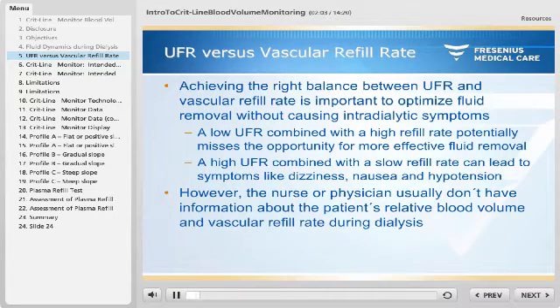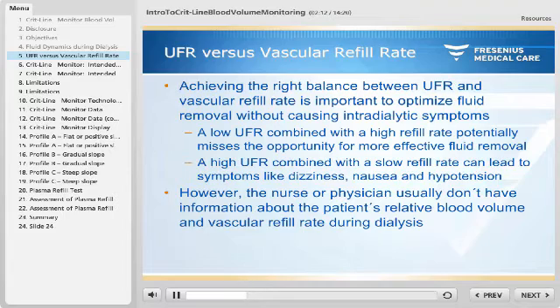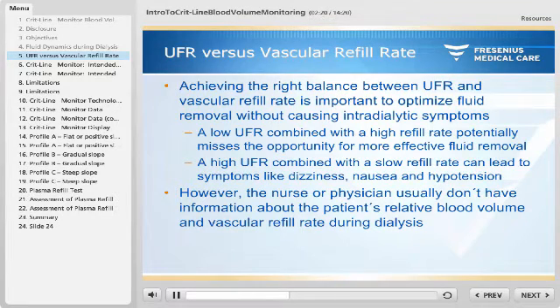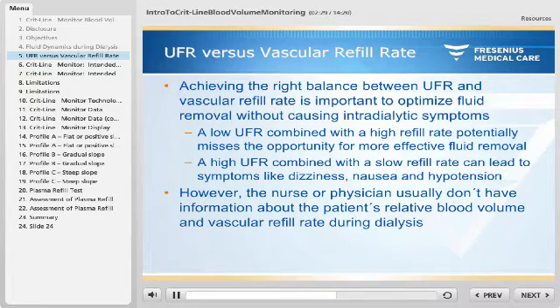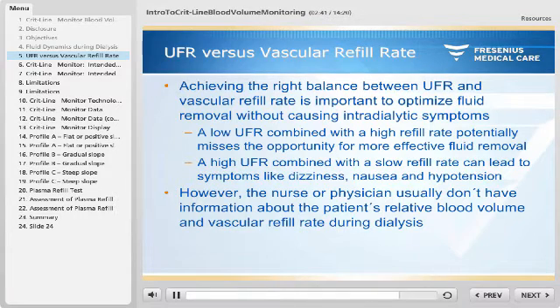When performing dialysis, achieving the right balance between ultrafiltration rate and vascular refill rate is important to optimize fluid removal without causing intradialytic symptoms. A low ultrafiltration rate combined with a high refill rate could potentially miss the opportunity for more effective fluid removal. A high ultrafiltration rate combined with a slow refill rate can lead to symptoms such as dizziness, nausea, and hypotension. In many cases, the nurse or physician does not usually have information about the patient's relative blood volume and vascular refill rate during dialysis. The lack of this information is what led to the design of the CRITLINE monitor.